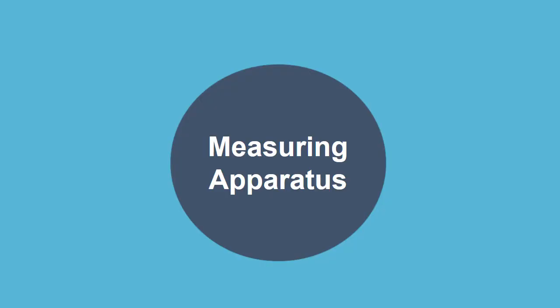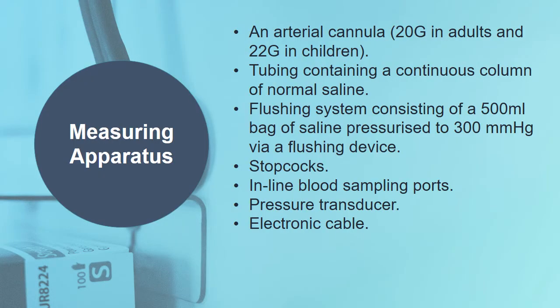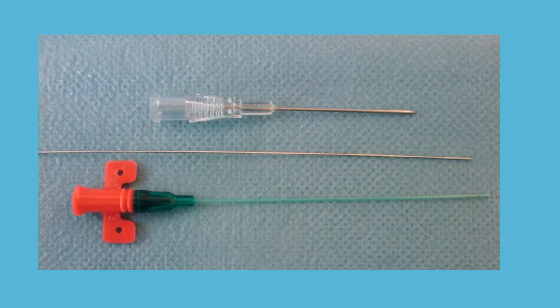For the measuring apparatus we need: a 20-gauge arterial cannula for adults and a 22-gauge cannula for children. We need non-compliant tubing — tubing that is rigid and resistant to bending — containing a column of normal saline. We need a flushing system consisting of a 500 mL bag of normal saline pressurized to 300 mmHg via a pressure infuser and flushing device. We also need stopcocks, in-line blood sampling ports, a transducer, and an electronic cable.